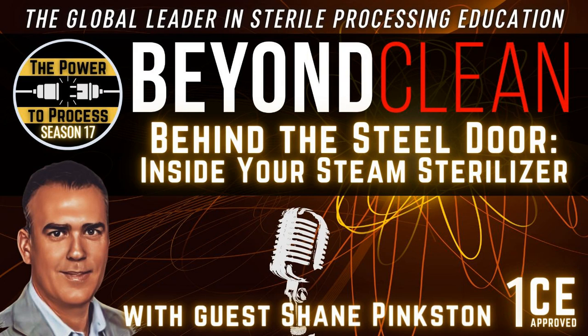Human nature is that we want to cram as much stuff as humanly possible into something. I make the analogy of the dishwasher at home where somebody is trying to cram something on top of a plate and invariably something doesn't come out clean. So how is that any different in a sterilizer with steam penetration? It's kind of the same concept — if you don't have access to the point, how do you kill the microorganism that may be there?